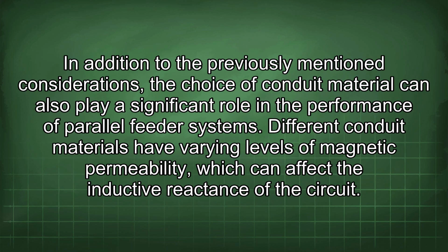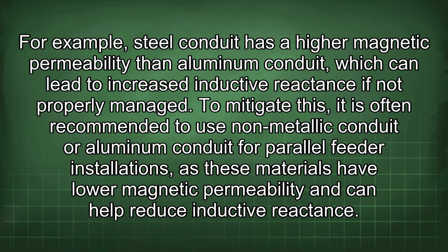In addition to the previously mentioned considerations, the choice of conduit material can also play a significant role in the performance of parallel feeder systems. Different conduit materials have varying levels of magnetic permeability, which can affect the inductive reactance of the circuit. For example, steel conduit has a higher magnetic permeability than aluminum conduit, which can lead to increased inductive reactance if not properly managed. To mitigate this, it is often recommended to use non-metallic conduit or aluminum conduit for parallel feeder installations, as these materials have lower magnetic permeability and can help reduce inductive reactance.